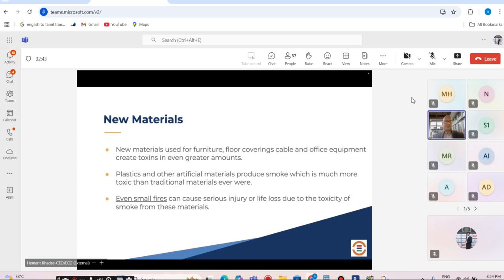Nowadays, building construction materials are getting into different forms and innovations. There are a lot of construction materials being used which are not necessarily flame retardant or fire retardant. So how your building interior finishes are getting inside the building, could be hotel, hospital, office, residence. Two parameters are to be evaluated when it comes to building material, which we all know are addressed in codes and standards: smoke development index and flame spread index. There are classifications given in the codes and standards, A, B, C or 1, 2, 3, for how the rating has been given to that particular material. It could be carpet, curtains, linens in the hotel especially, or any of the occupancy.